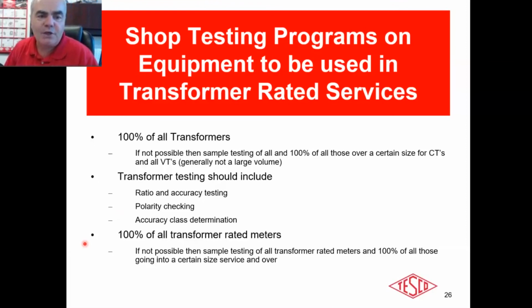Like to know how easy it is to go overburden. 100 feet of number 12 has a certain amount of burden. Yes, it is. First of all, Matt, it is fairly easy to go overburden, especially with the length of the cable. And yes, you can actually do the calculations. If you need some help with that, we'd be happy to do that offline.